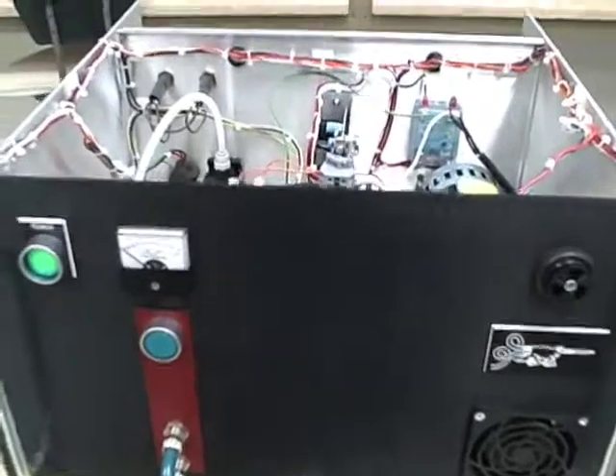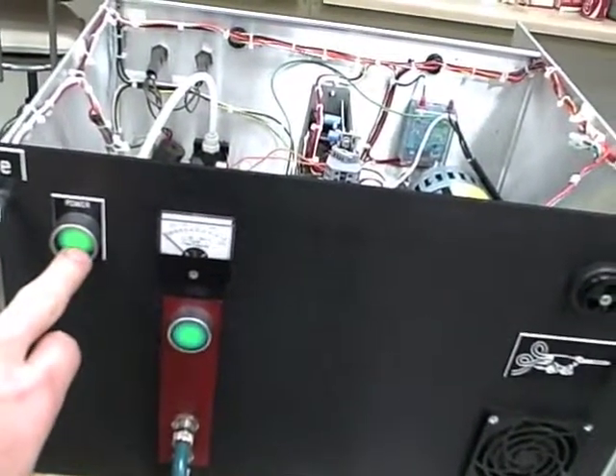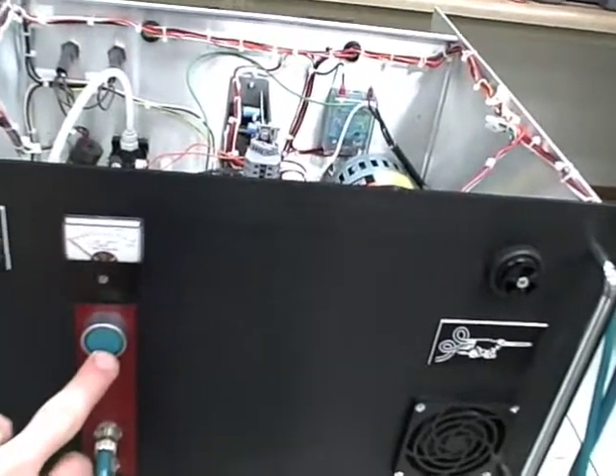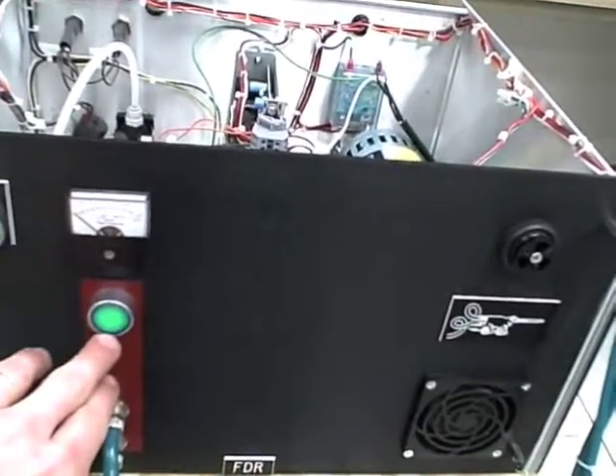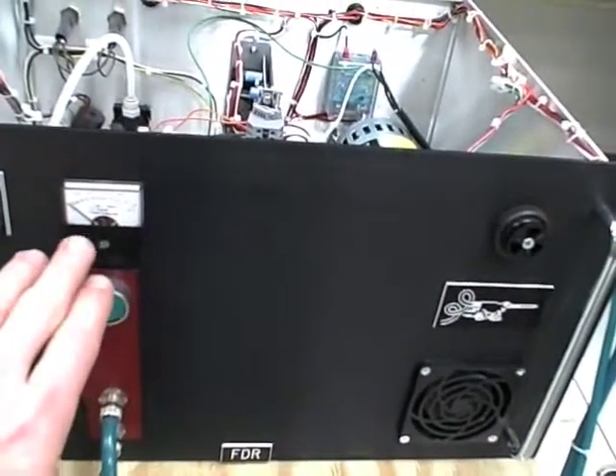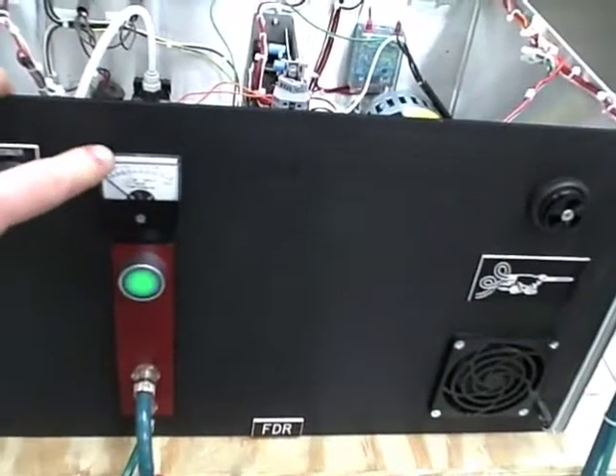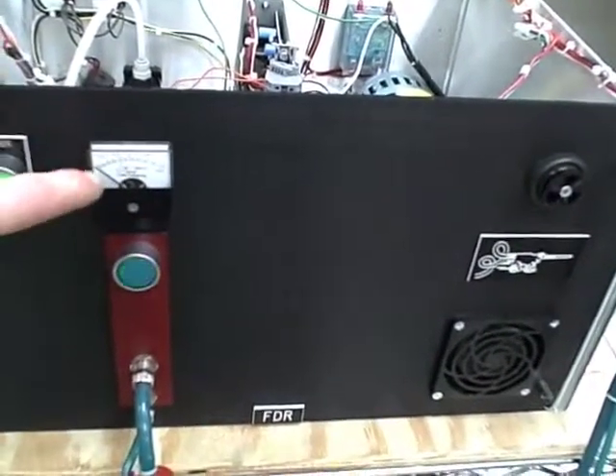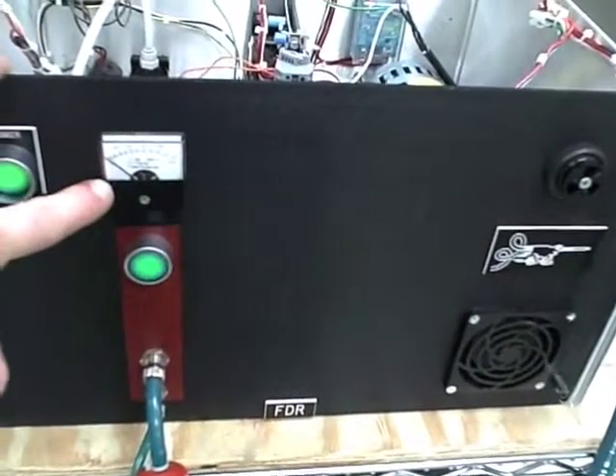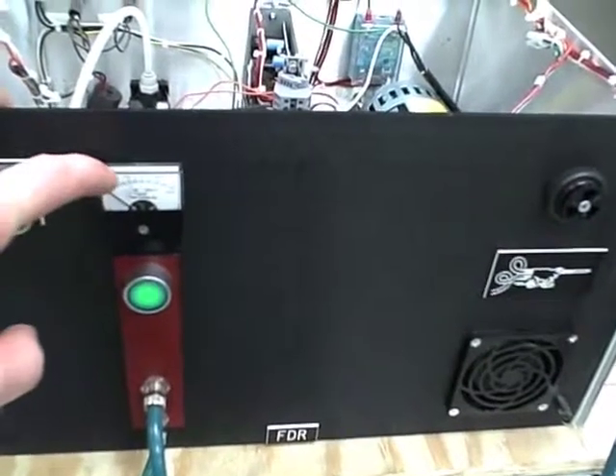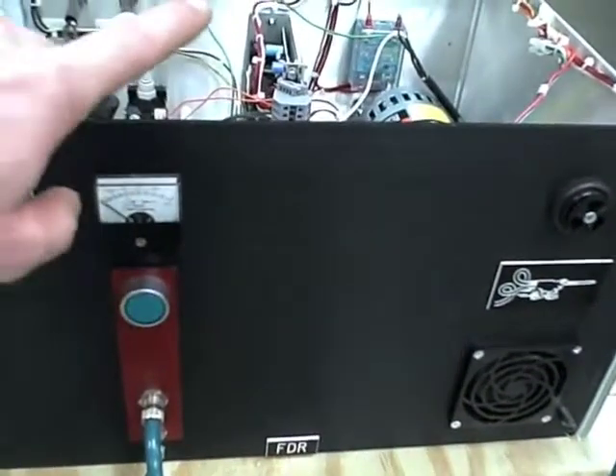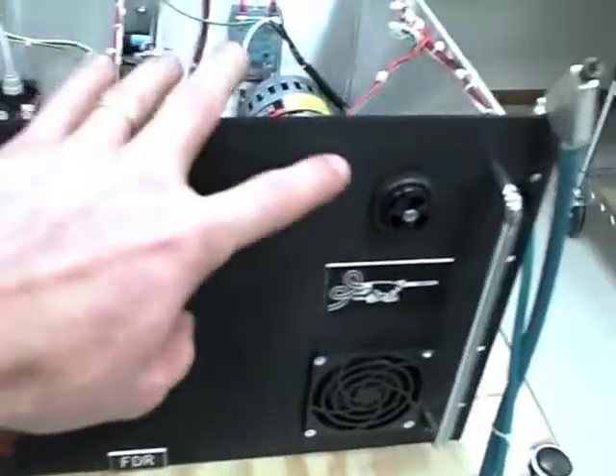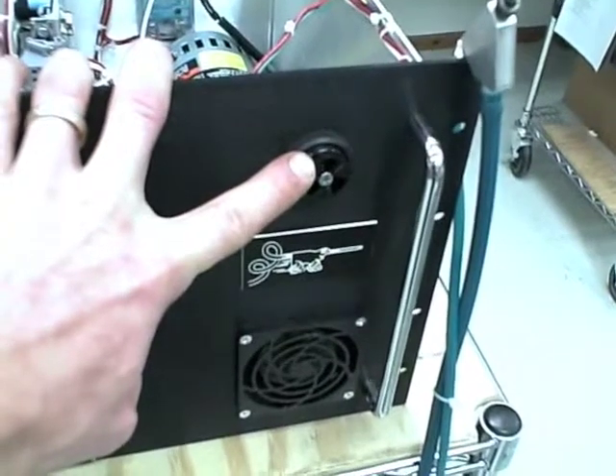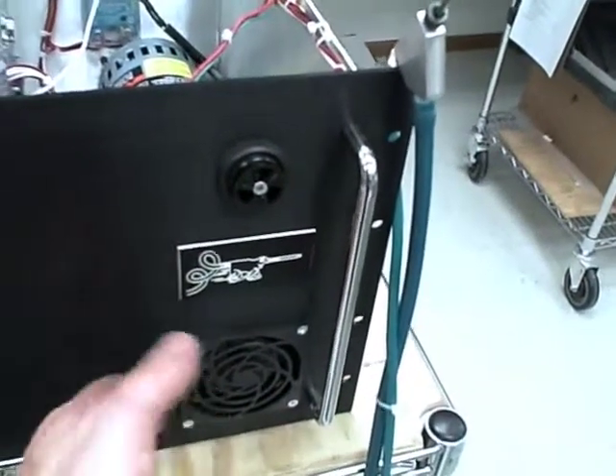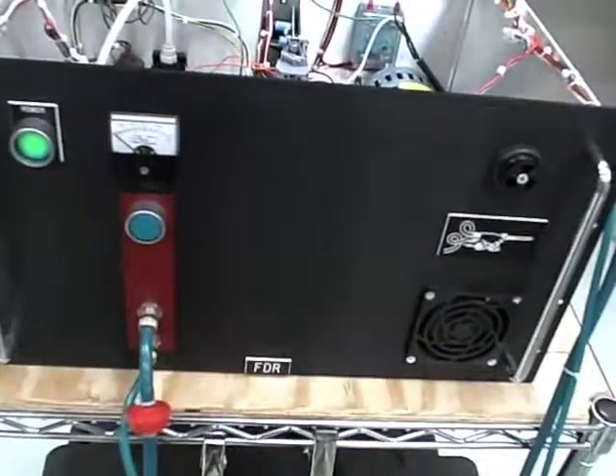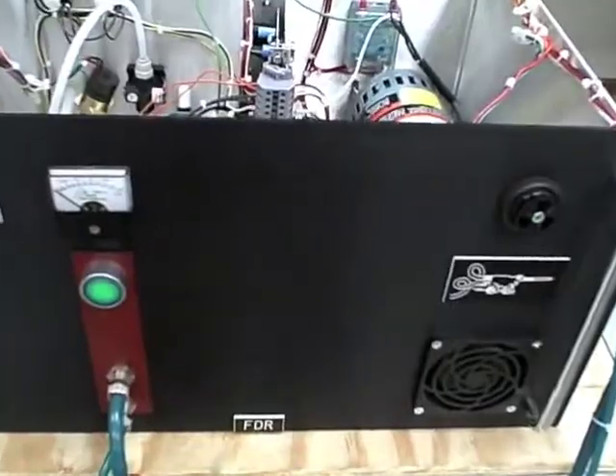On the front of the machine, you'll notice just a basic power button that just turns the machine on and off. The start button, that's going to be for this particular line. The RSGe is a one-line machine only. And then the meter on the front is going to be showing the argon percentage as the unit fills. You can also use it for troubleshooting and calibration as a calibration aid to see when 5 volts in the back is equal to 100%. And then the beeper, which signals the end of the cycle, and the fan, which just keeps the unit from getting overheated as the pump runs for longer time as the units are being filled.